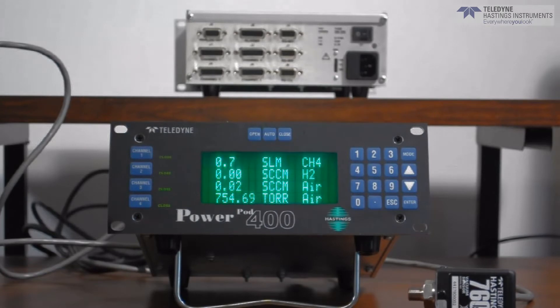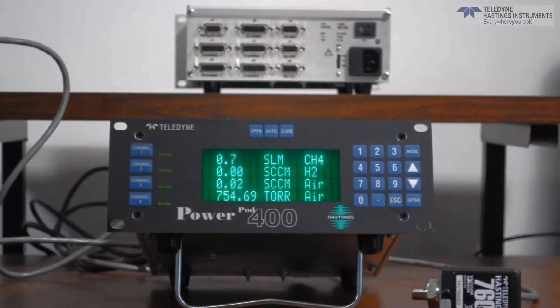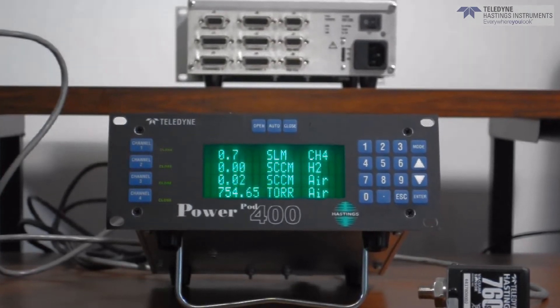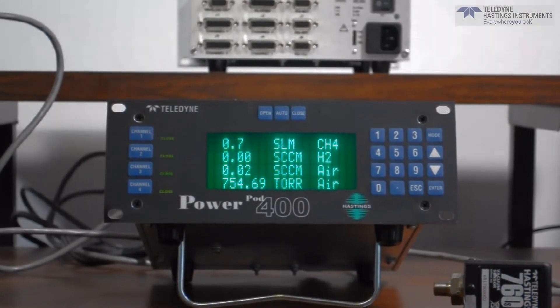Let's start by taking a look at the front panel. One of the key benefits of the PowerPod 400 is that all four channels can be viewed at the same time. There's no need to surf through channels or turn knobs to see which MFC is reading. The units of measure and process gas can be entered for each individual channel.